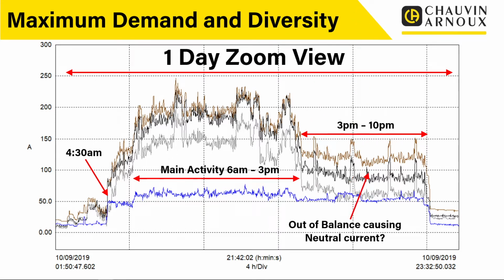Now, in that period between 3 p.m. and 10 p.m., we can see that the loads tend to mirror each other on the phases, but we've still got quite a lot of neutral current, so it does look like it's out of balance quite a bit there. So again, that might be an indication that there are improvements or savings to be had by improving the balancing within the installation. Because when we are looking at maximum demand, and this ties in with what we'll talk about later on with energy efficiency, sometimes you can identify things where you think, it looks like maybe the grey phase is not very highly loaded. So could we move some circuits onto that? Could we move things around, and that'll bring down the overall maximum demand of the installation to a more acceptable level?